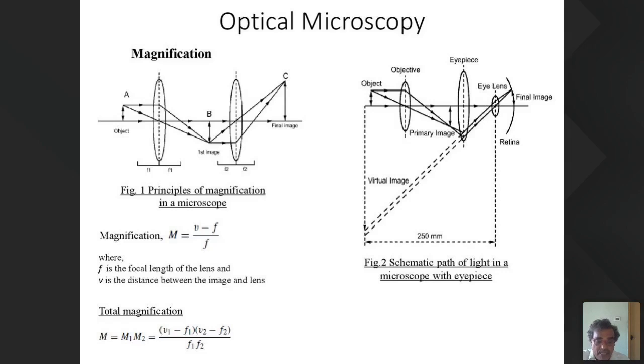If we think about the important things in the optical microscope, one is magnification. The magnification of the microscope can be calculated by linear optics. It is the ratio between the distance between the image and the lens, and the focal length of the lens. If you want a higher magnification, you should have a shorter focal length. The total magnification of a compound microscope is the product of the magnifications of the objective lens and the projector lens.